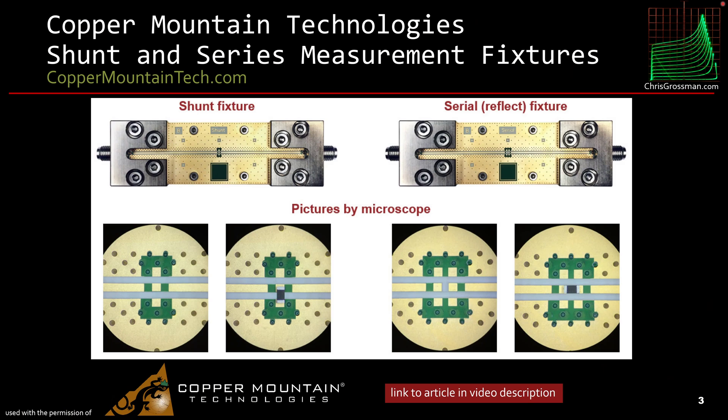Now let's talk about fixtures. This is one I found while I was doing some research. This is a beautifully designed coplanar, grounded actually, grounded coplanar microstrip with the picket fence, and this is one I found that has a lot of wires along the side of it. It's bolted down to probably a machined piece of metal to keep it flat and keep it from flexing. It may even be glued down with conductive epoxy. It's gold plated, so when you put parts on, you'll get good contact. And, you know, machined, matched connectors, this thing will work well into the gigahertz region.